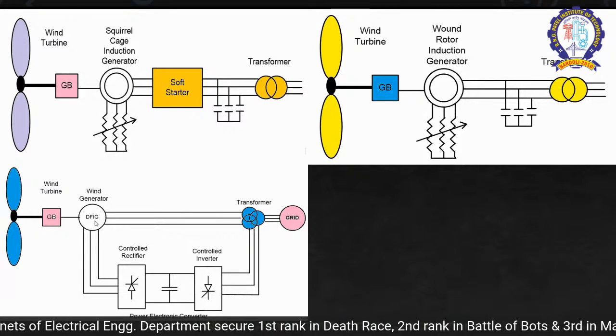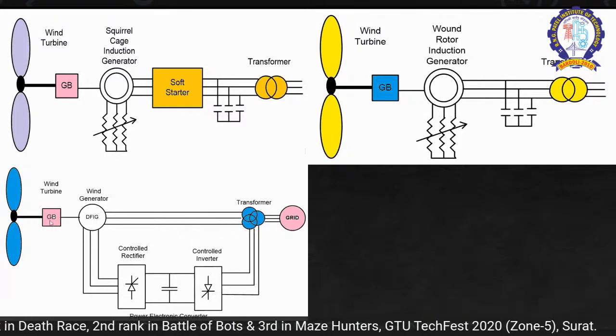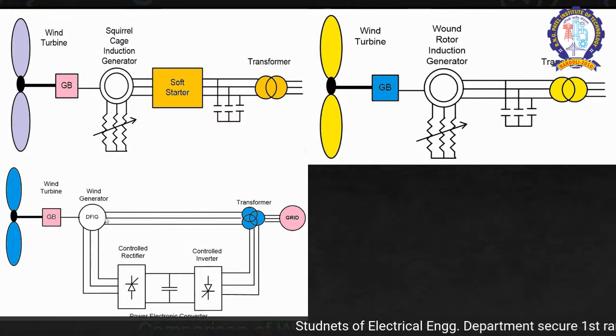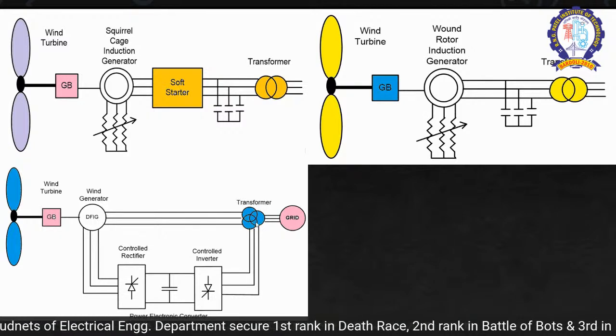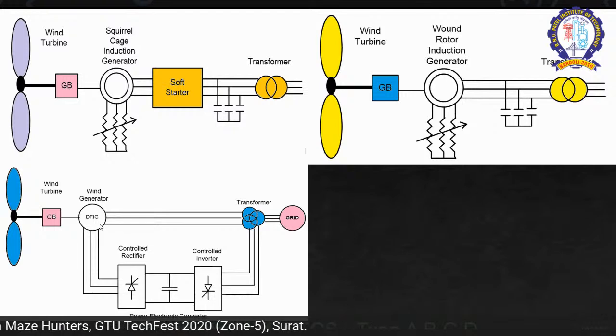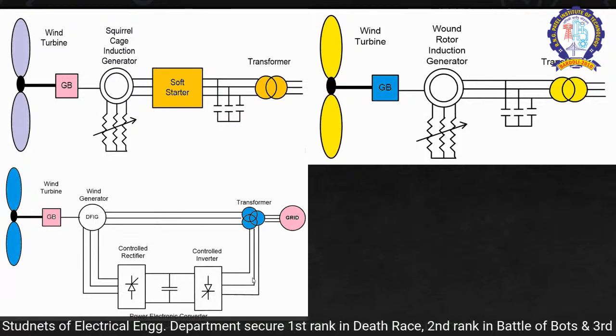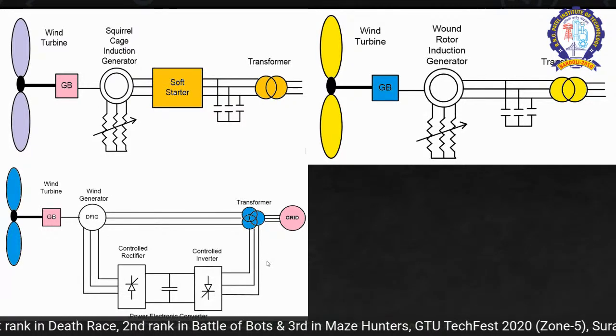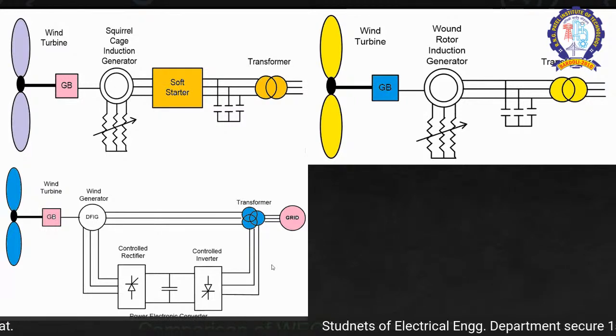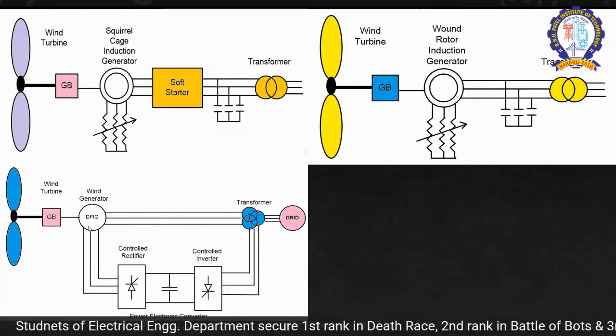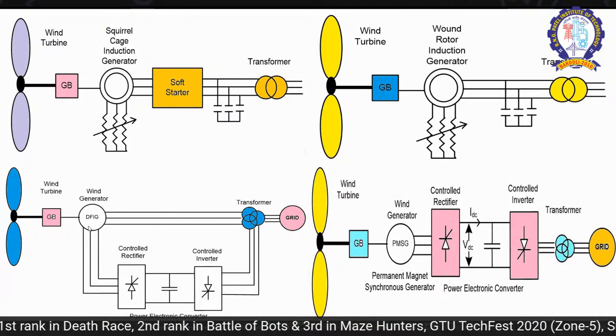The DFIG can be covered by stator and rotor itself, because the wind turbine is connected through the gearbox to the rotor and the power is generated through the stator, and both rotor and stator are connected with the transformer and the grid. We have a controlled rectifier and a controlled inverter, so we can manage the power from both sides. Usually, the power is shared 70% from the stator side and 30% from the rotor side. Here, the grid operator might observe connection and disconnection of the machine. These are things that can be discussed in this session only at a glance. You will find detailed chapters in theoretical books on how you can change the operation of the DFIG and other generators. And the last one is the type D system.